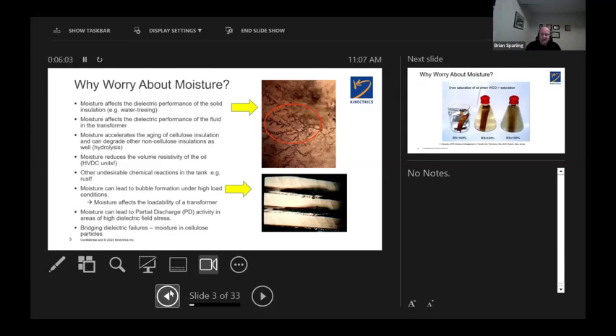So we're looking at this, and the other thing to be concerned about, with that picture on the lower right, is the evidence of what we call bubbling, when the moisture in the paper on the conductors in the windings reaches the point of being too much, and the conductor temperature is at the right spot where normally the moisture moves in and out of the paper by diffusion. It moves back and forth. It becomes so wet that the diffusion stops and you have bubbles. What you see there are water vapor bubbles or steam on top and below.